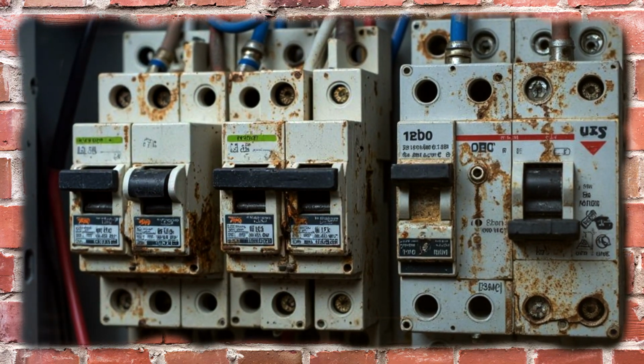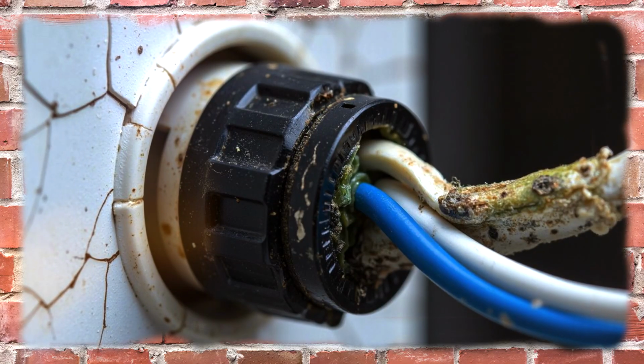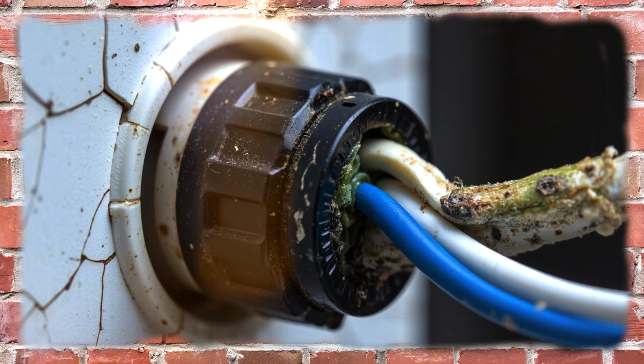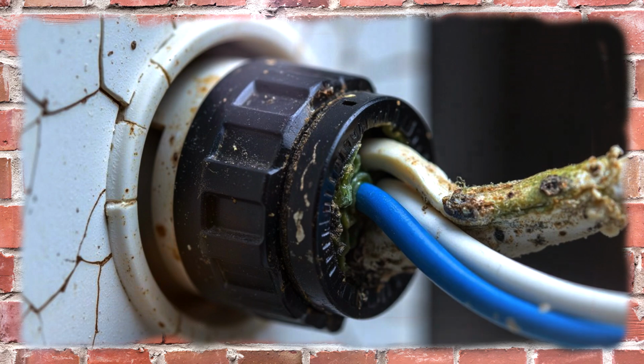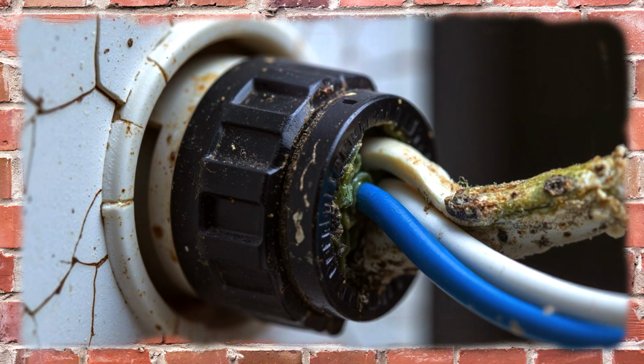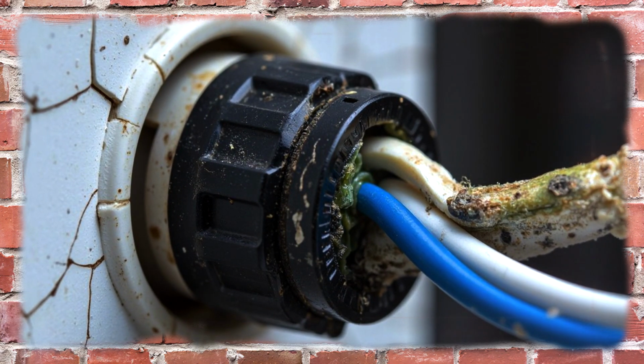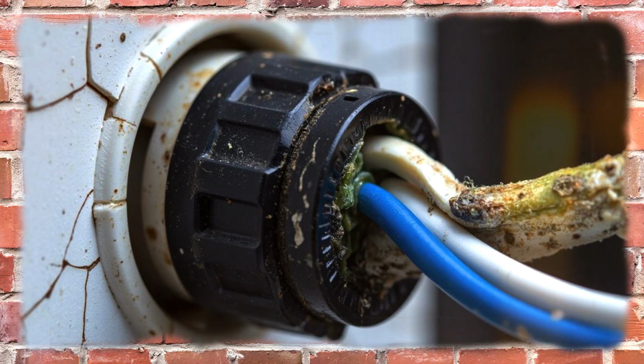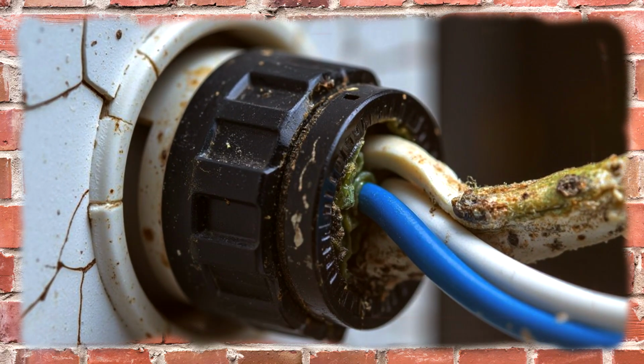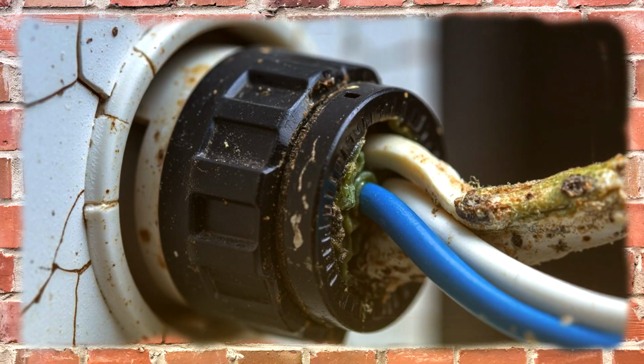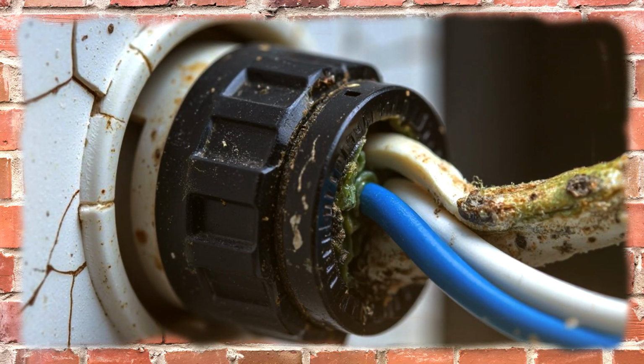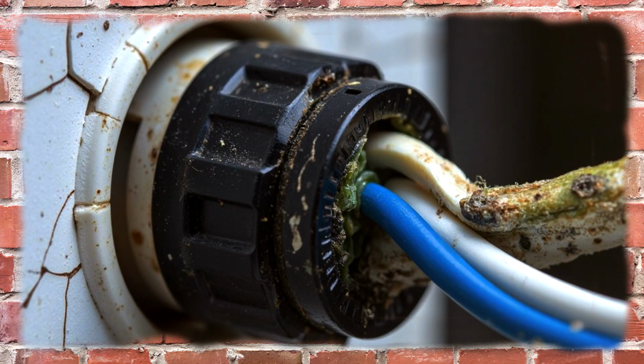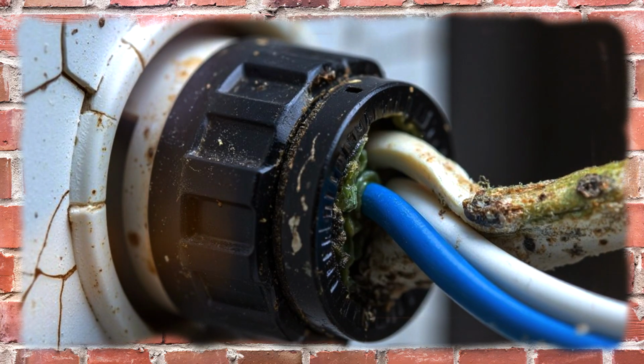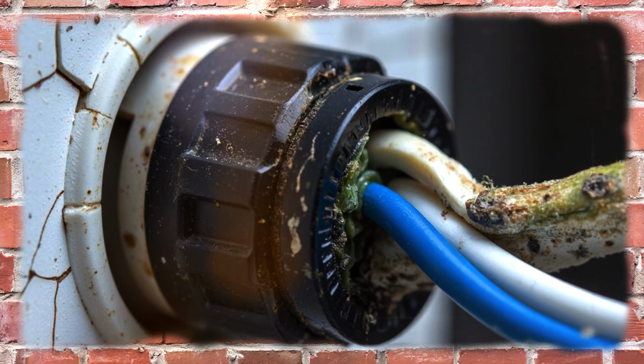In the US, the focus rests on ground fault circuit interrupters, GFCIs, mandatory wherever water contact risk exists. And these devices are so sensitive they trip at 5 mA within 25 milliseconds, faster than human pain response, saving lives. Per the National Safety Council, household electrocution deaths dropped over 70% after mandatory GFCI adoption.